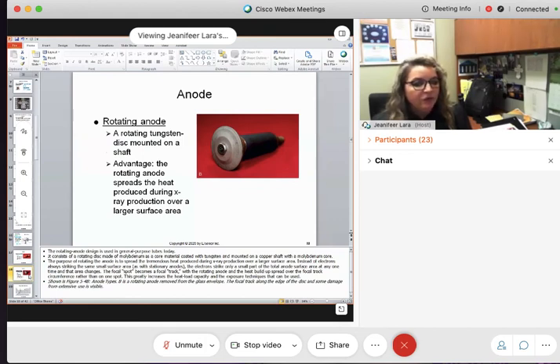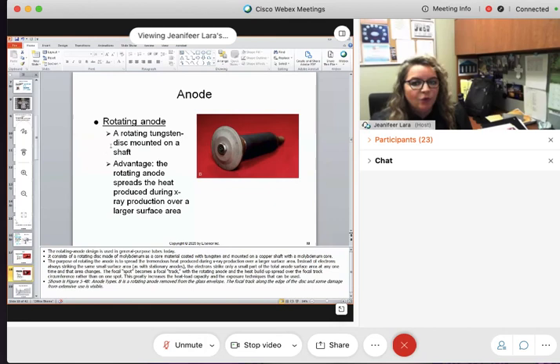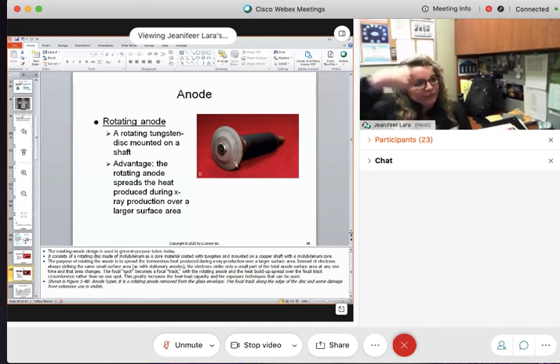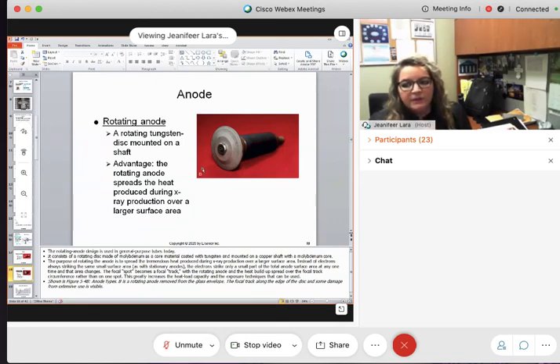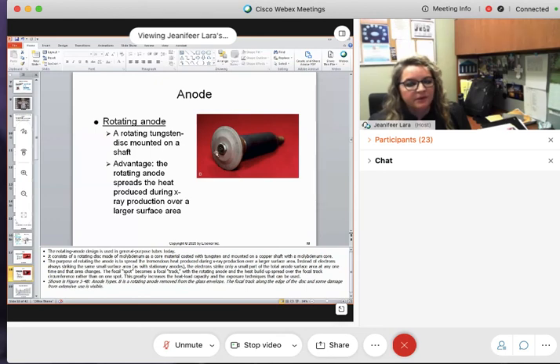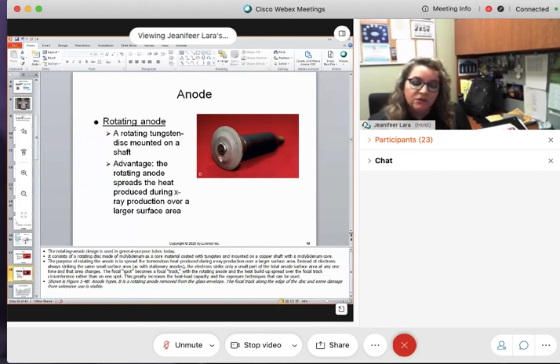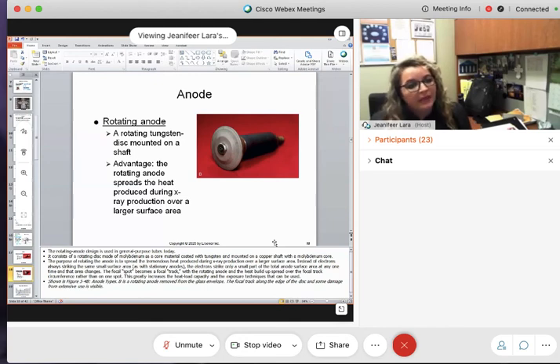The second type — better — is the rotating anode. This whole thing is called a disc. The disc rotates really, really fast so that when the electrons come over and strike the anode, they hit different parts of the disc rather than the same place. This advantage over the stationary anode means it moves the converted heat around the glass or metal envelope and into the oil that lines the protective housing.